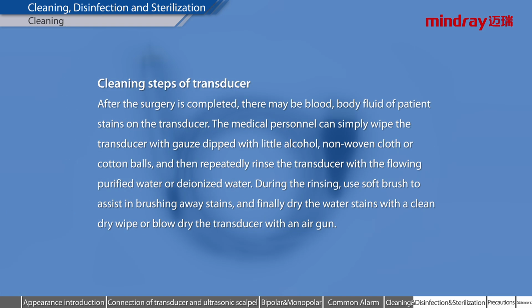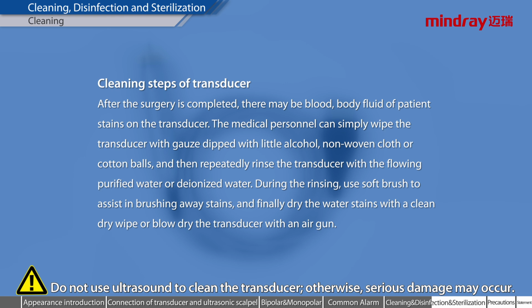Cleaning steps of the transducer. After the surgery is completed, there may be blood, body fluid, and patient stains on the transducer. The medical personnel can simply wipe the transducer with gauze dipped in a little alcohol, non-woven cloth, or cotton balls, and then repeatedly rinse the transducer with flowing purified water or deionized water. During the rinsing, use a soft brush to assist in brushing away stains, and finally dry the water stains with a clean dry wipe or blow dry the transducer with an air gun. Do not use ultrasound to clean the transducer, otherwise serious damage may occur.